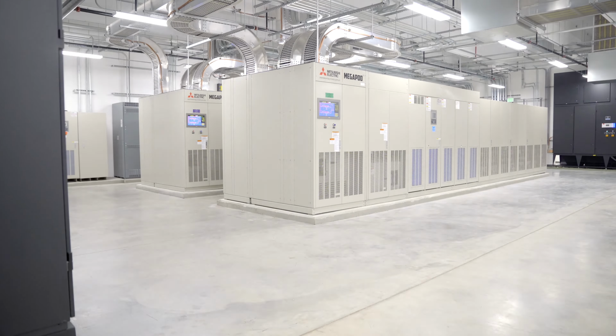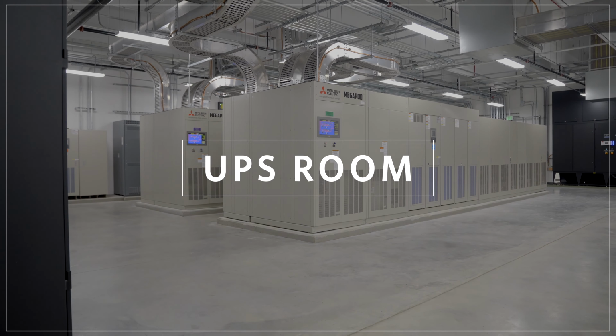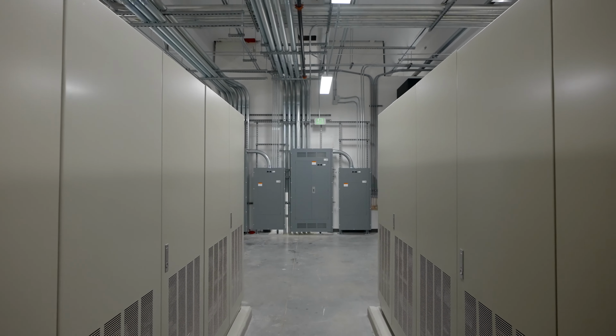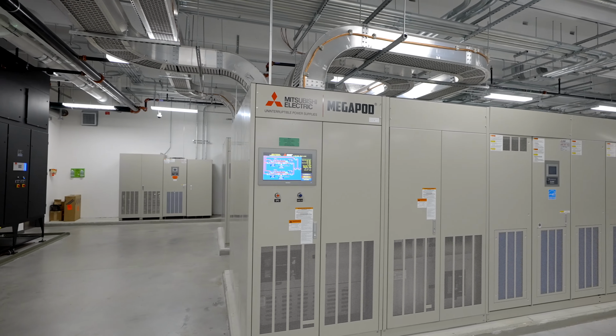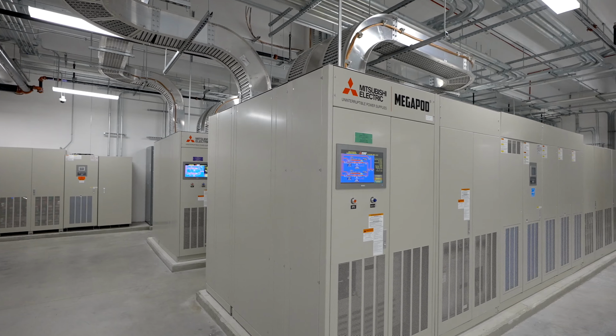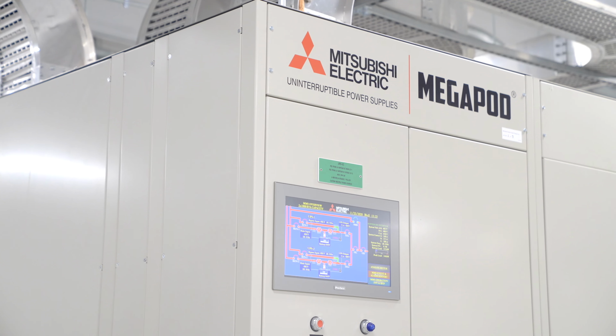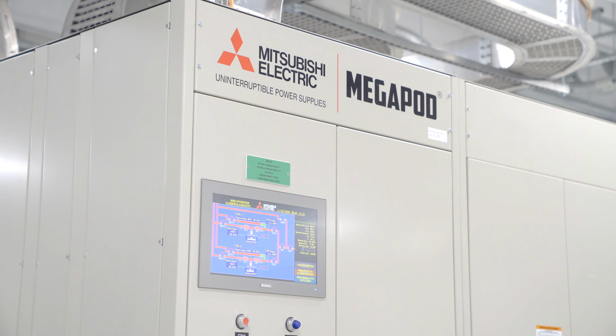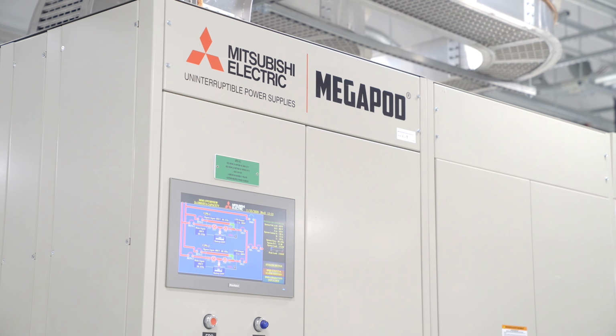Power to this facility is provided by Dominion Power's Herndon substation. The UPS topology backing up this computer room is a 4-to-make-3 distributed redundant system. Each system is also backed up by a maintenance bypass UPS, which allows for UPS-provided power when a UPS goes offline or is isolated for maintenance. The double conversion UPS system supports a 6-minute battery runtime when at 100% load.